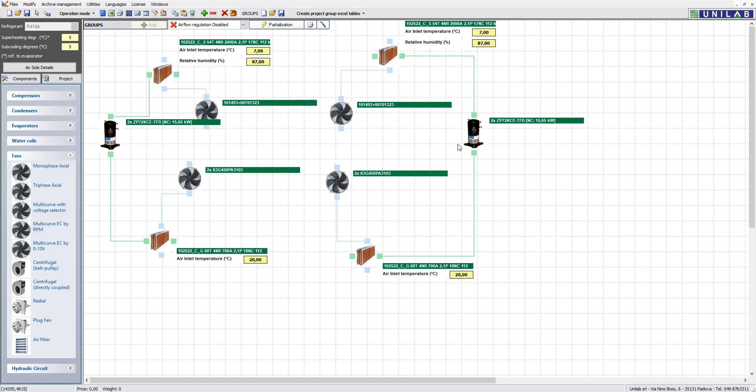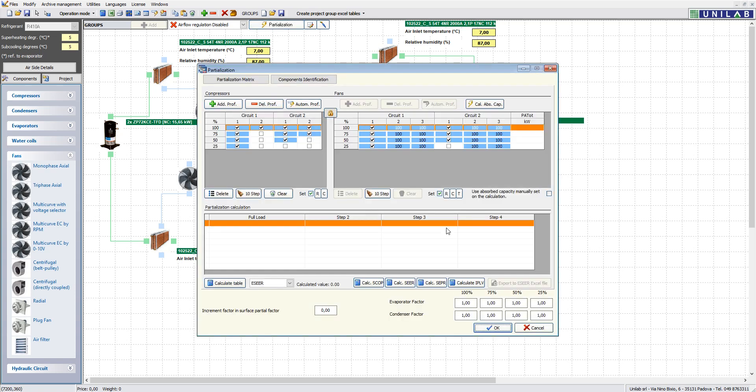Shark also lets you partialize the compressors. It lets you partialize scroll and screw compressors, and it is possible to add up to 20 levels of partialization — specifying for each level the performance of the inverter compressor, marking the on/off square for scroll compressors, or in percentage for screw compressors. You can also set the partialization of the fans if the unit is an air-water chiller, and if you use a variex, the program will adapt the fans' air flow to increase the condensing temperature as well.